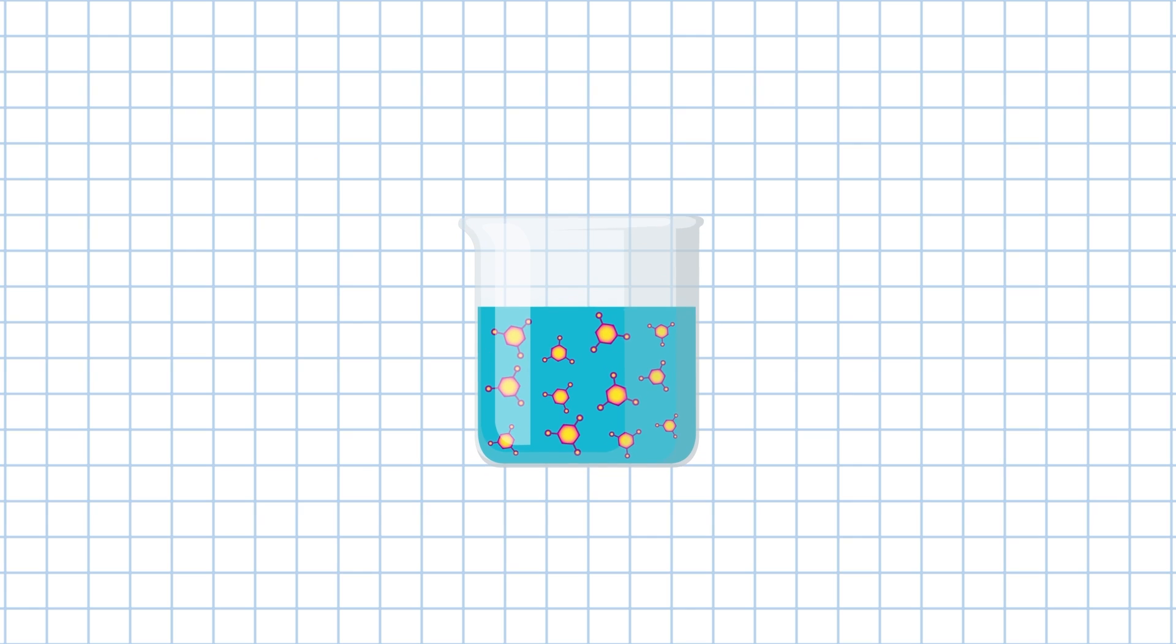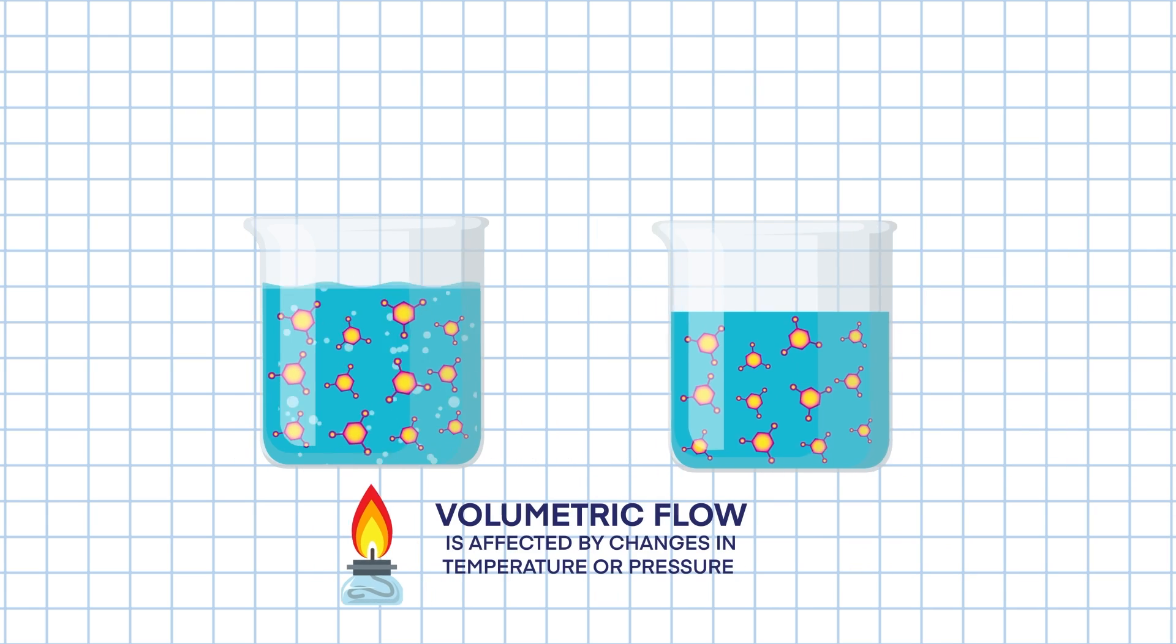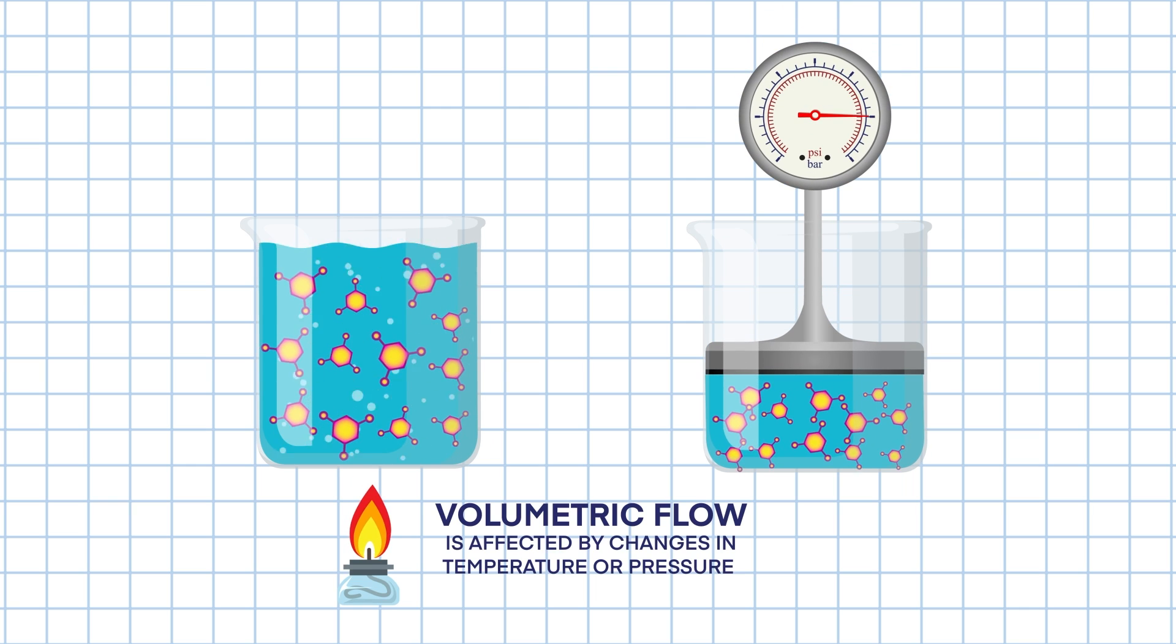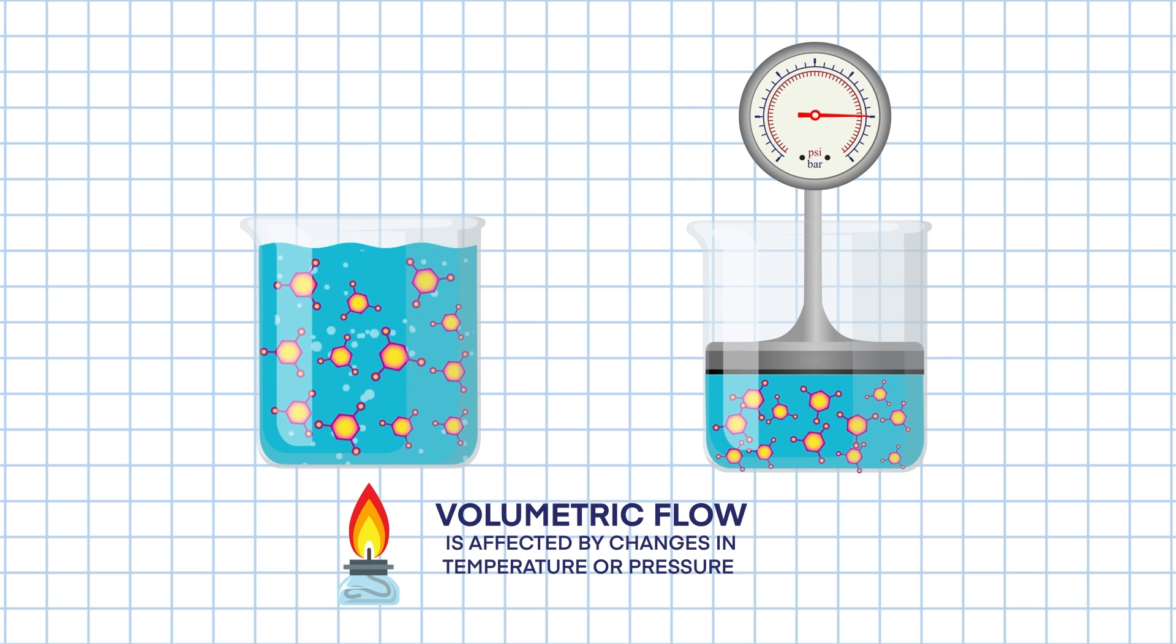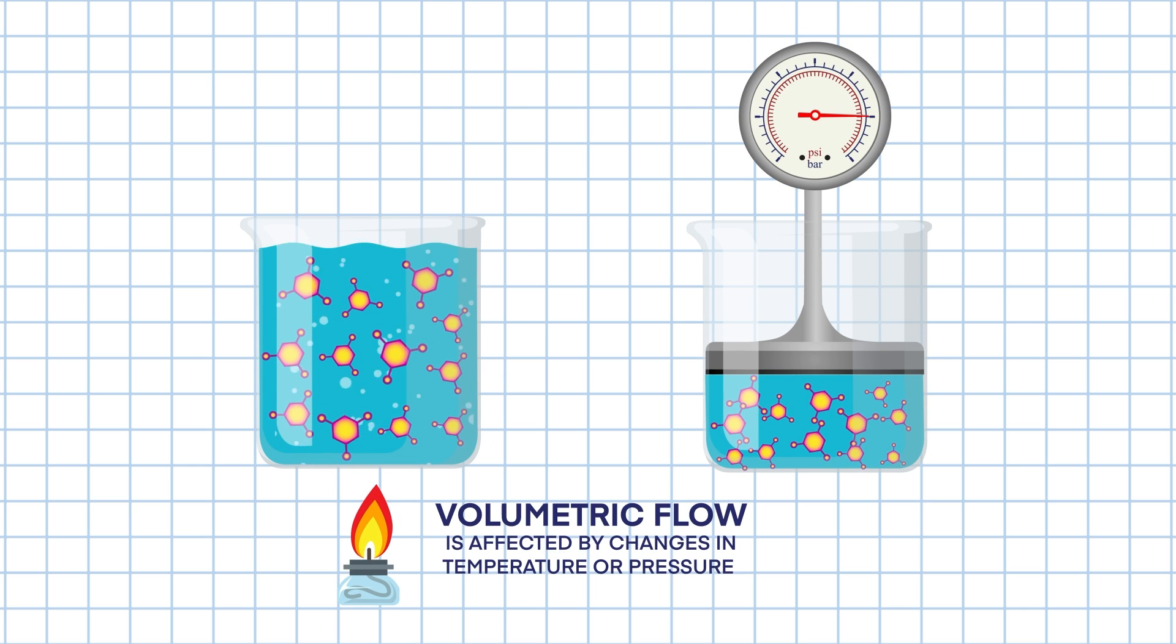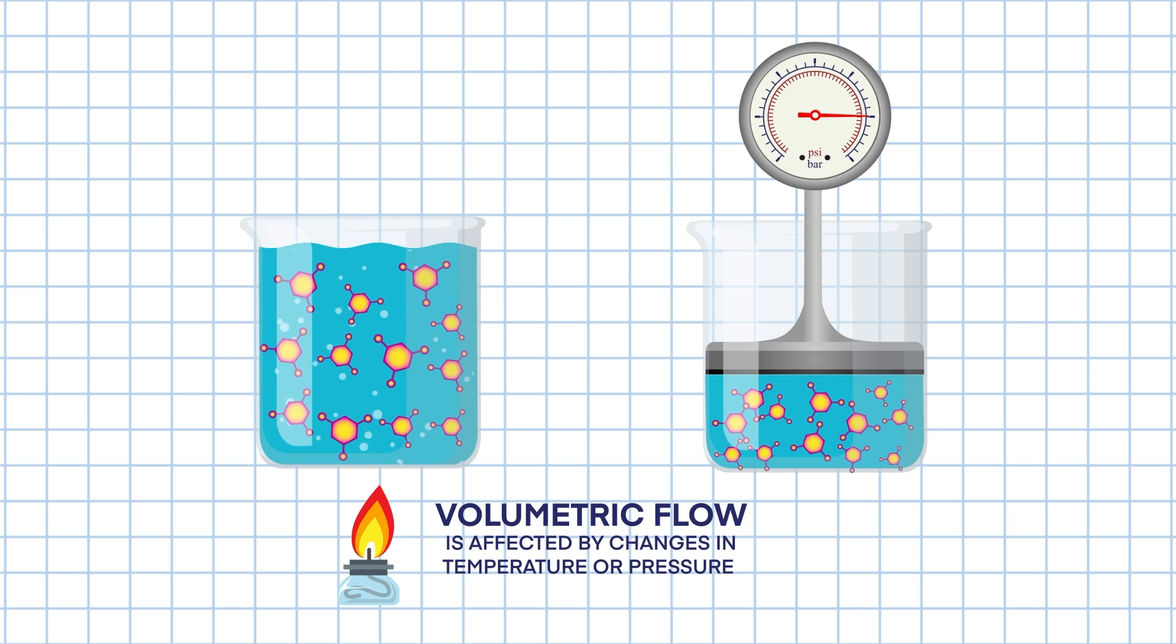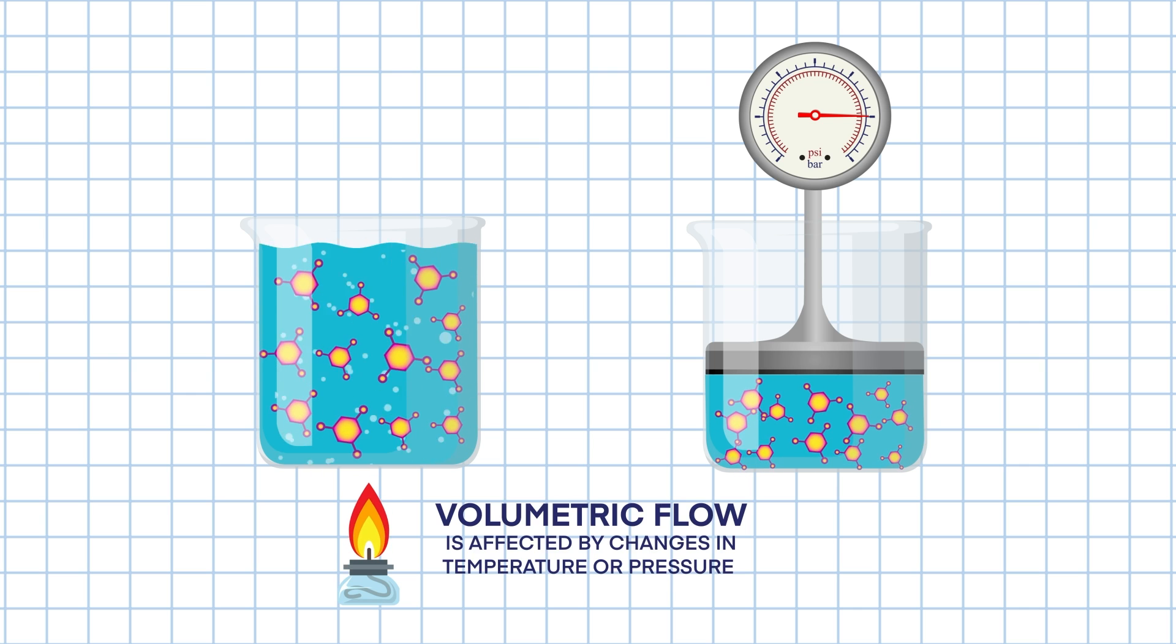And unlike mass flow, the volumetric flow of a substance is affected by changes in temperature and or pressure, since temperature and pressure fluctuations can change the density of the substance. Hence, when measuring volumetric flow, changes in temperature and pressure of a substance at the measurement site should be compensated for.